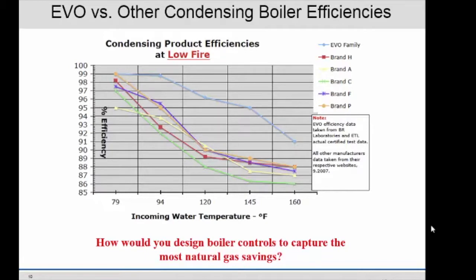Here are the performance curves. This happens to be the boilers we're using right now, and these are other manufacturers, so they're not all created equal. You've got to really look at their performance data. On condensing heating equipment, it's always based on some parameter. On a boiler, it's the incoming water or the return temperature. That's how you improve that efficiency. The further you can get that return temperature down, the better. The older systems are usually a supply temperature of 180 and a return of 160. You want to make sure you design these systems, if you can, and change them to where you have a bigger temperature difference and a lower temperature. Don't do a 160 return. Try to get down to 120. You get a much higher efficiency out of those boilers.